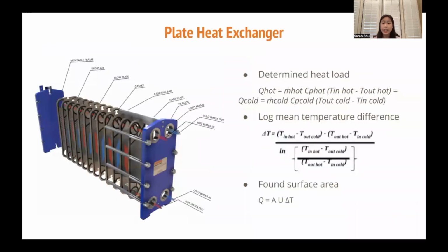So both the plate heat exchanger and the heat pipe system, which will be shown on the following slide, are waste heat recovery techniques. The objective of waste heat recovery techniques is to circulate waste heat developed during industrial processes back into the system. The plate heat exchanger consists of metal plates stacked parallel to each other. Two liquids, one hotter and one colder, are pumped through the plates, and heat transfers from the hotter to the cooler liquid.